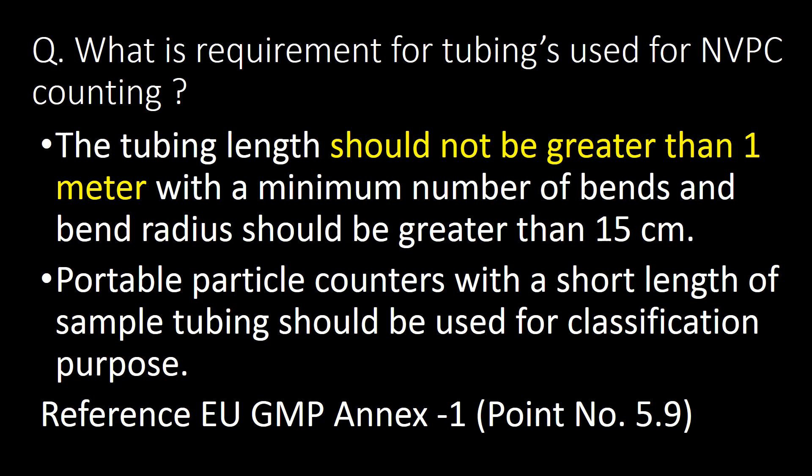What is the requirement for tubing used for NVPC counting? The tubing length should not be greater than 1 meter with a minimum number of bends, and the bend radius should be greater than 15 cm. Portable particle counters with a short length of sample tubing should be used for classification purposes. Reference: EU GMP Annex 1, Point No. 5.9.